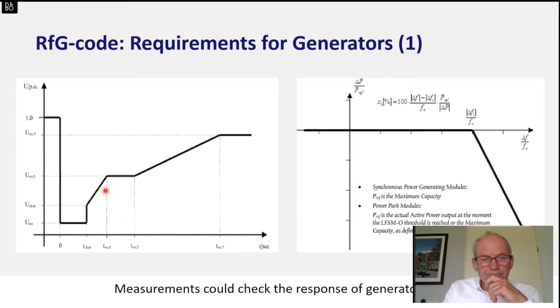So you have to give some requirements for your generators, not only for the response to voltage and frequency, but also for the capability to ride through voltage dips. When there is a voltage dip somewhere in the network, it should not be the case that all these renewable generators disconnect from the network. They have to stay connected and should support the stability of the network. So the impact on voltage dips is quite important, and also how they react to the voltage dips.